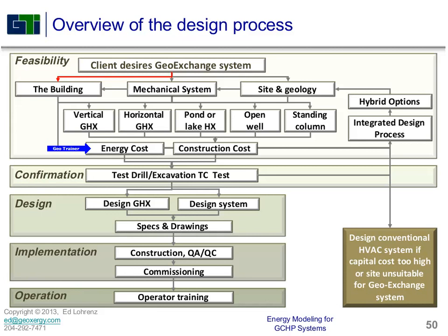The 2 most important things where we've been able to reduce the size of ground loops, and we've done that, we reduced the size of ground loops by as much as 40, 50, in some cases even up to 60% by going through this process: building a detailed energy model of the building and the mechanical system that's going in there. Then we found we can improve the efficiency, we can reduce the energy cost for the building, and we can reduce the cost of building the system in the first place. We can have a huge amount of impact by doing these 2 things. We can't do much with this. It is what it is.